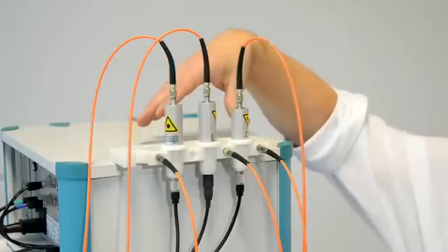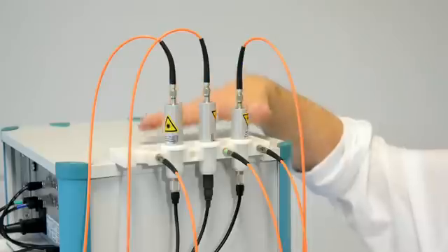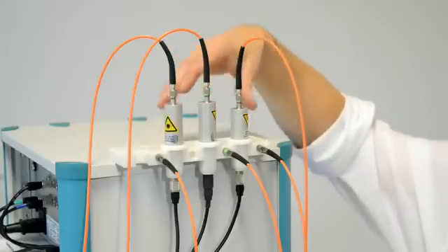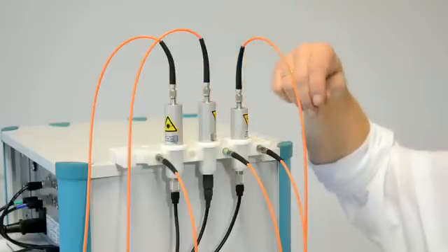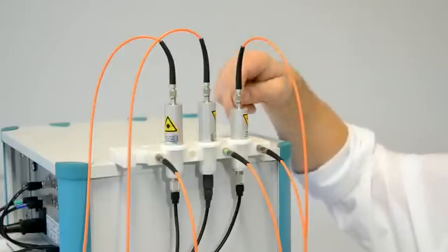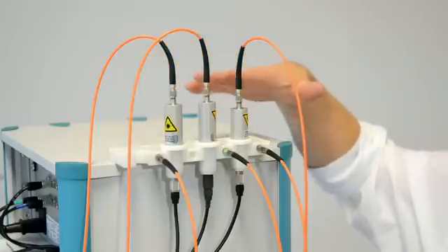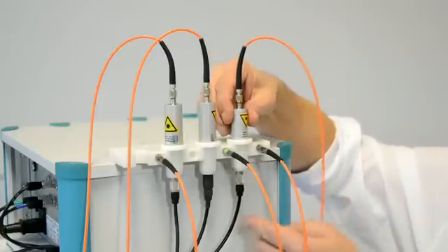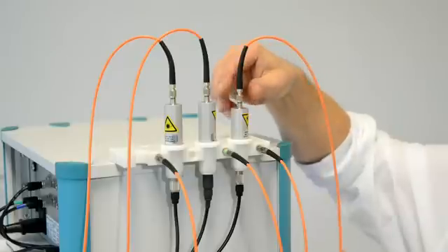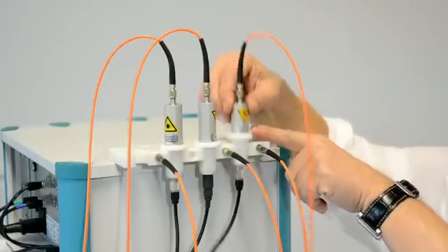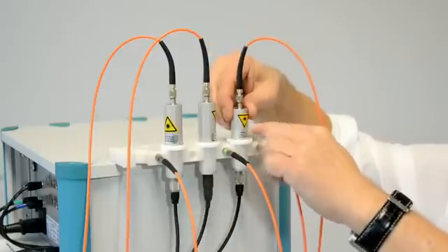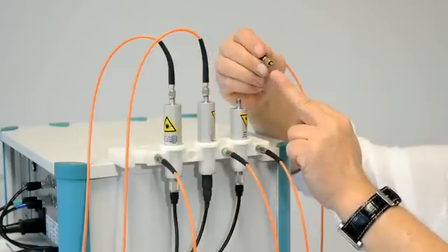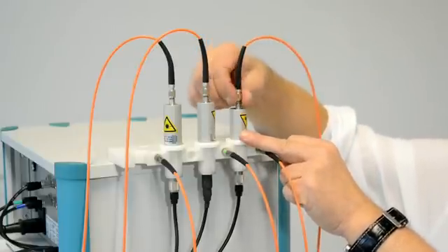I will now explain to you the laser technology. You see the three attached independent laser modules, one red, one green, and one blue. The big advantage is that the laser modules are not inside the device, but they are outside and plugged in on the back of the device. So if anything goes wrong with a laser, maybe a diode is not working, or maybe a cable is broken, the device has not to be sent to the company and opened, so the customer can repair most of the problems on this device himself. Here you see the glass fiber optics, which is screwed in the head of the module. Inside the module is the diode and the small driver board.